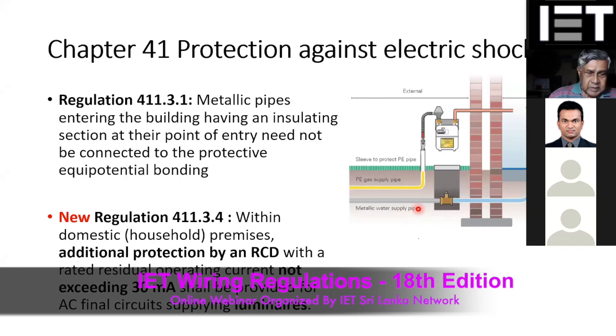But now what they are saying is you don't want to worry about the outside of the building, even though the metal pipeline is coming into the building. If the connection from the starting point, the metering point, to your installation is non-metallic, then you do not want to connect the metal part outside the building to the earthing system, that is, the equipotential bonding.